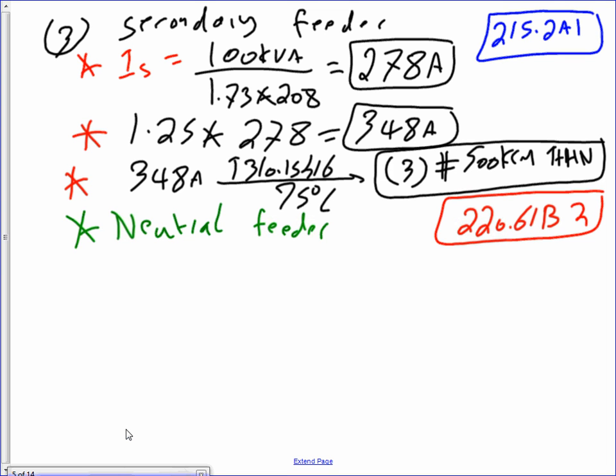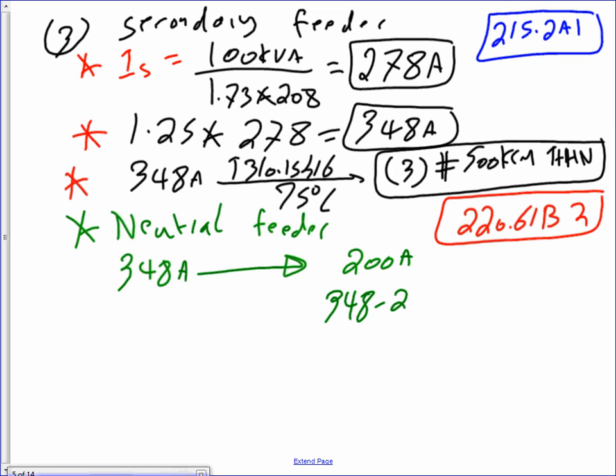So what I typically would do is I take the full load amp, which is where we are here, 348. So take the 348 amps that you sized your phases on, the first 200 amps, leave them alone. This is from 220.61(B)(2), guys. And anything above that, you take 348 minus 200, cut it by 0.7, add them up, and you're going to end up with 304 amps, 304 amps.